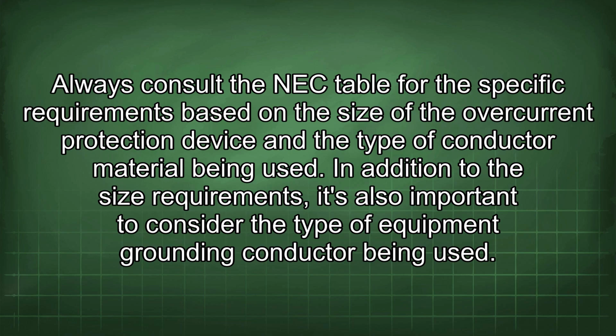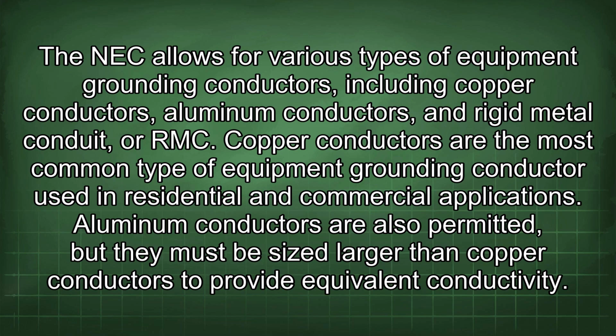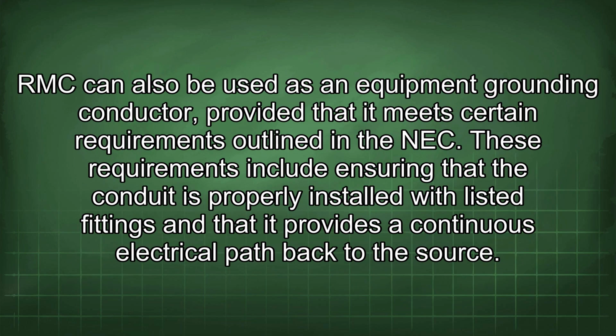In addition to the size requirements, it's also important to consider the type of equipment grounding conductor being used. The NEC allows for various types of equipment grounding conductors, including copper conductors, aluminum conductors, and rigid metal conduit, or RMC. Copper conductors are the most common type of equipment grounding conductor used in residential and commercial applications. Aluminum conductors are also permitted, but they must be sized larger than copper conductors to provide equivalent conductivity. RMC can also be used as an equipment grounding conductor, provided that it meets certain requirements outlined in the NEC. These requirements include ensuring that the conduit is properly installed with listed fittings and that it provides a continuous electrical path back to the source.